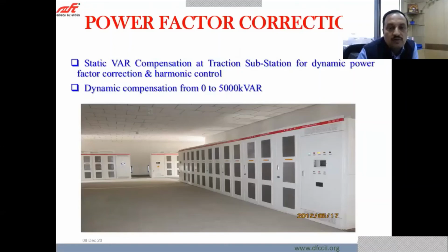This is the power factor correction. I told in the beginning, this dynamic reactive power compensation is being adopted by WDFC so as to avoid any penalty because of low power factor or because of injection of harmonics in the system. Our compensation range is from 0 to 5000 kVAR, which will be sufficient for the system design capacity level.